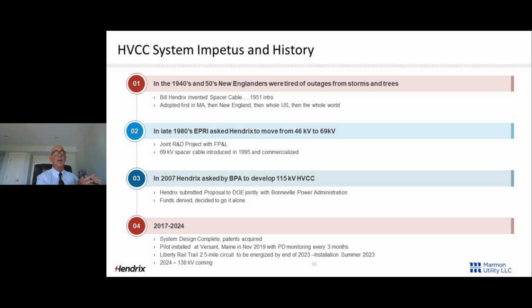In the late 80s, Electric Power Research Institute asked Hendrix to move from 46, we were only at 46, up to 69 kV. So we had a joint R&D project with Florida Power and Light. We used their labs down in Juno. And 69 kV spacer cable was developed and introduced in 95 and commercialized. We now have 69 kV all over the place. In 2007, Hendrix was asked by BPA to develop 115 kV high voltage covered conductor. So we submitted a joint funding statement to the Department of Energy jointly with the BPA, but we were turned down, luckily turned down, and we decided to go it alone.